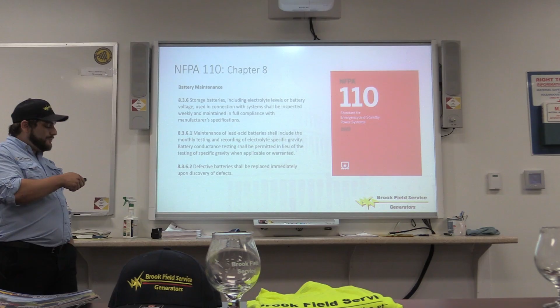Again, this is all for when disaster is happening, or inevitably will happen. Maintenance of the lead-acid battery shall include monthly testing and a recording of electrolyte-specific gravity. Battery conductance testing will be permitted in lieu of testing specific gravity when applicable or warranted. This is, I think, one of the more important ones here. Defective batteries will be replaced immediately upon discovery of defects. So obviously, if you test it and it's not testing right, I do another test.